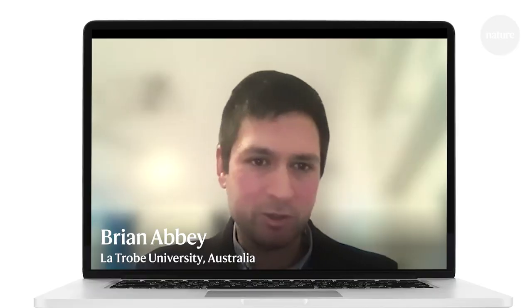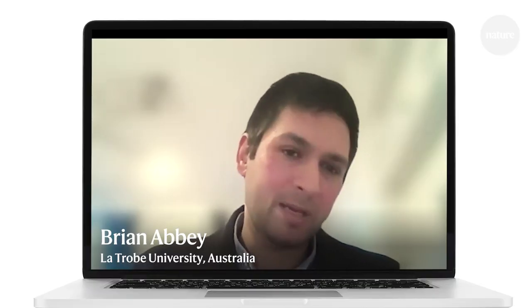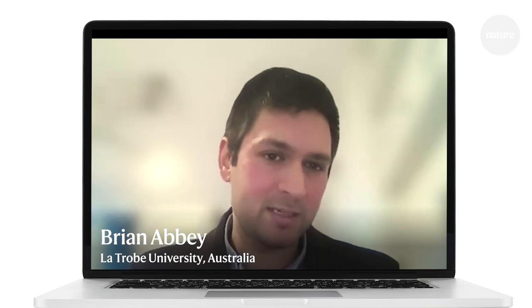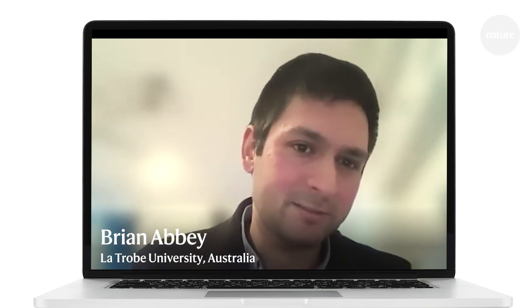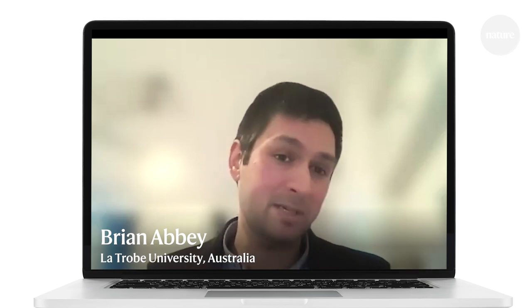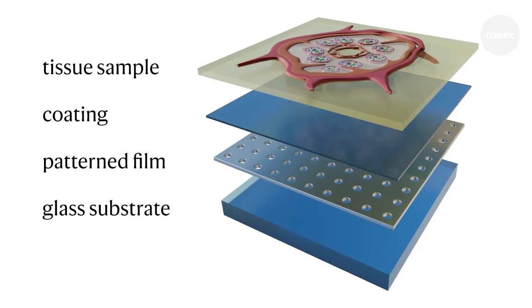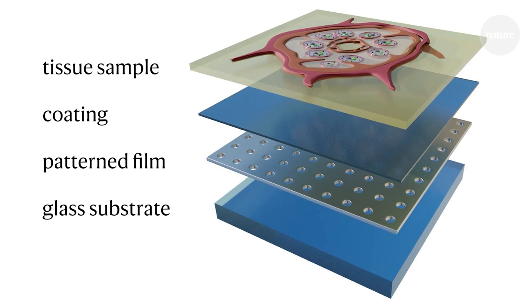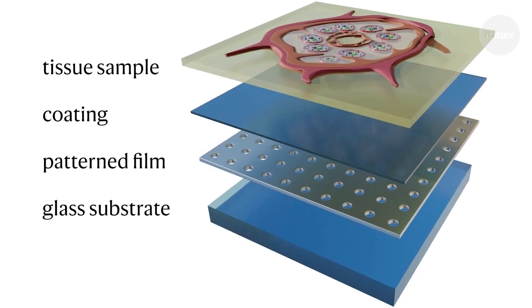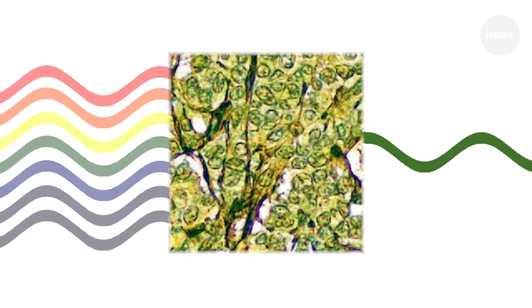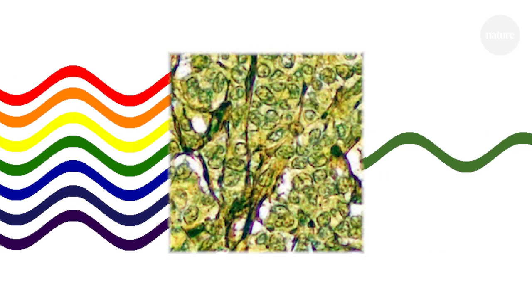We create a pattern across the entire slide, which basically makes the surface into a type of sensor. So your entire microscope slide then becomes a sensor. And depending on what gets put on that sensor, different wavelengths of the ambient light are absorbed. So if, for example, I put a healthy cell on our sensor, it absorbs a certain set of wavelengths. Then if you take a cancer cell and you place it on this sensor, it will absorb a different set of wavelengths because its composition is slightly different.